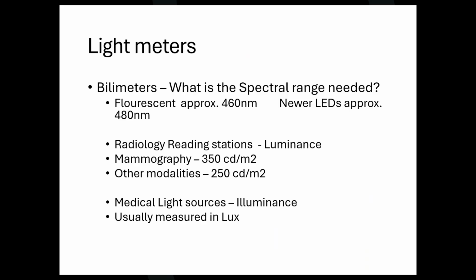All right, I'm going to go back to calibration here for just a second. I went on site and was talking to someone and said, okay, your bilimeter has to come back for calibration. And they were like, well, no, I'm sorry, our previous company did them here, why can't you? It's because I have a $20,000 light bulb, and it is strictly controlled current, I've got distances. And I said, just curious, how did the other person do that? They said, well, he's got a calibrated bilimeter. He holds one right here, he holds the other right here, and if it reads the same, it's calibrated.